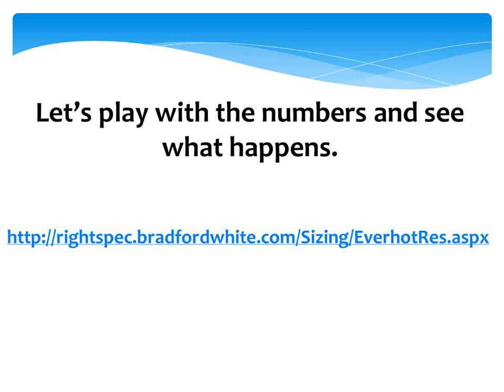So the example I have down here is a Chicago homeowner. We're talking about a Delta T, a temperature rise, of 75 degrees. So we're talking about 40-degree incoming water, and we're doing a 115 outlet. We don't have to worry about it in the summertime because the incoming water temperature is going to be quite a bit higher. So we size for those worst-case applications.